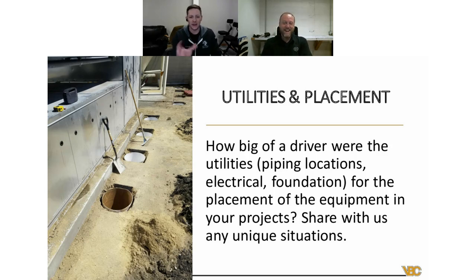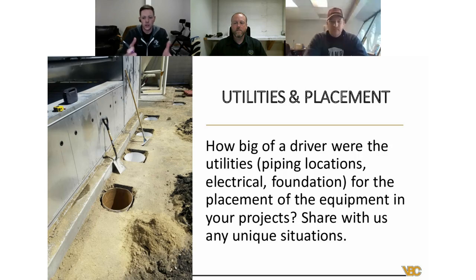I couldn't quite pick up the tail end, so I might be reiterating what Glenn said, but as far as the projects we get into, we're in a different situation—a much more rural area with a lot more free space around us. However, with a chiller specifically, it's pretty common for anyone designing or growing their brewery or production facility to want to keep that glycol chiller somewhere no one ever sees, which is an advantage from an aesthetic standpoint and a space-saving standpoint, tucking it out of sight, out of mind. So the biggest thing for us, and the biggest thing I always fall back on, is as-built drawings from construction and other expansion projects.